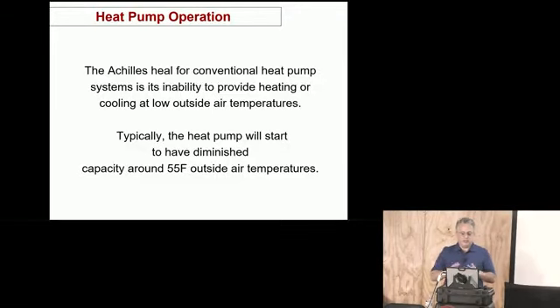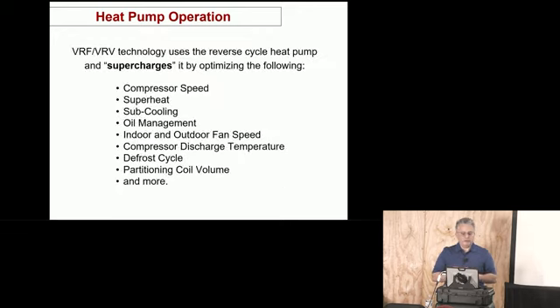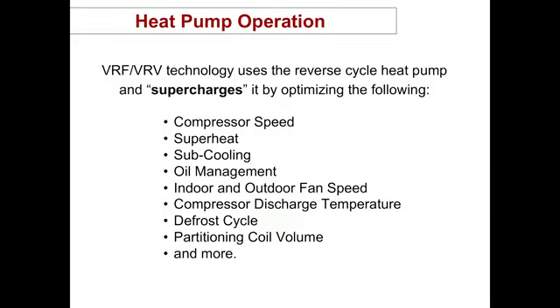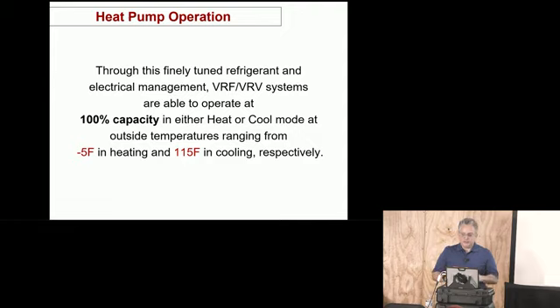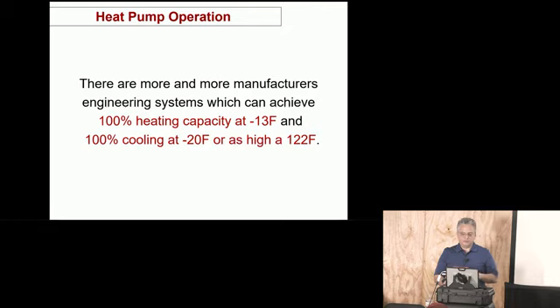However, the Achilles heel for a conventional heat pump system is its inability to provide heating or cooling at low outside air temperatures. Typically, the heat pump will start to have diminished capacity around 55 degrees outside air. However, VRF technology uses the reverse cycle heat pump and supercharges it by optimizing the following. So each one of these components is monitored and manipulated by the software. Through this finely tuned refrigerant and electrical management, VRV systems are able to operate at 100% capacity in either heat or cool mode at outside air temperatures ranging from -5 degrees to 115 degrees, respectively. There are other systems that can perform even greater.